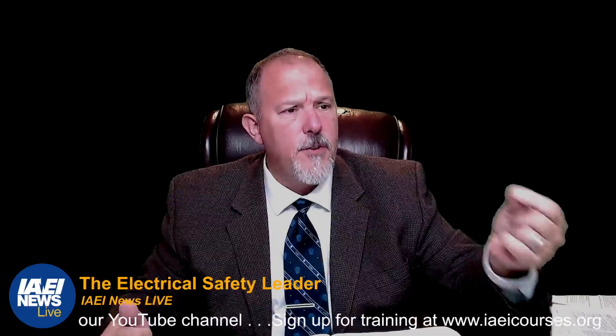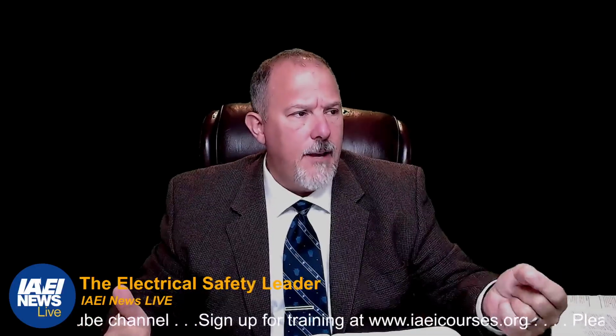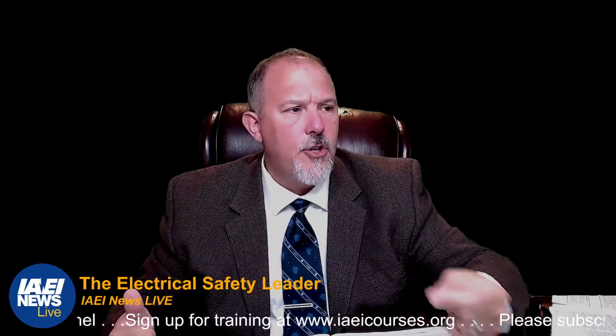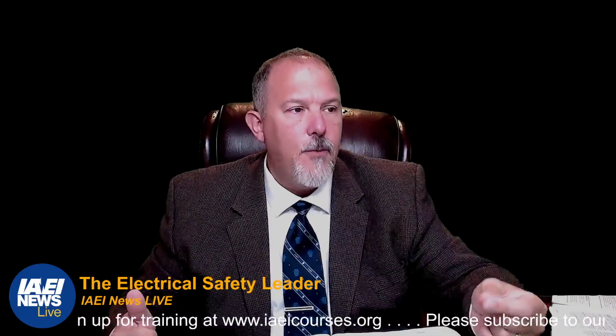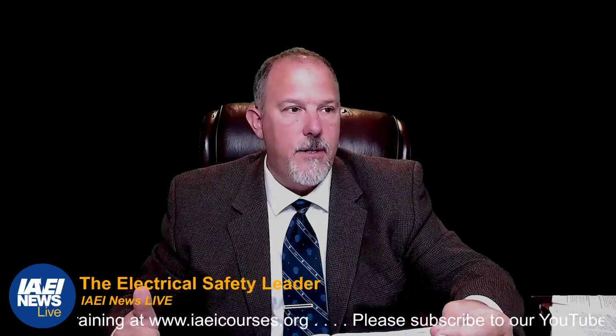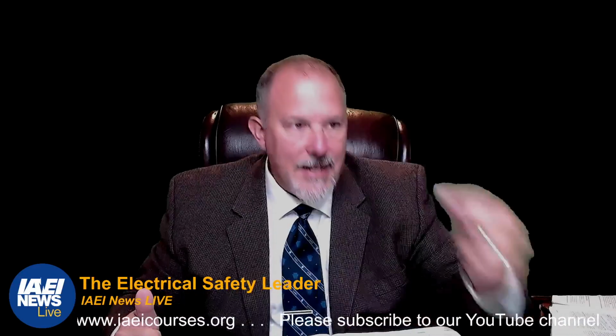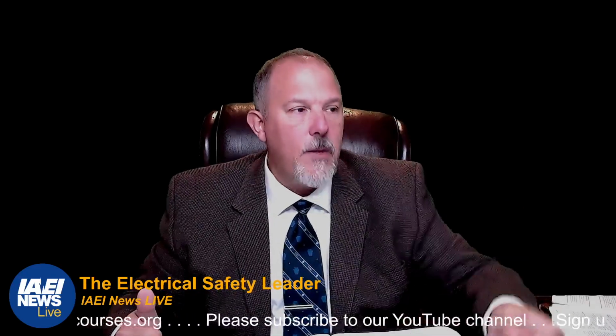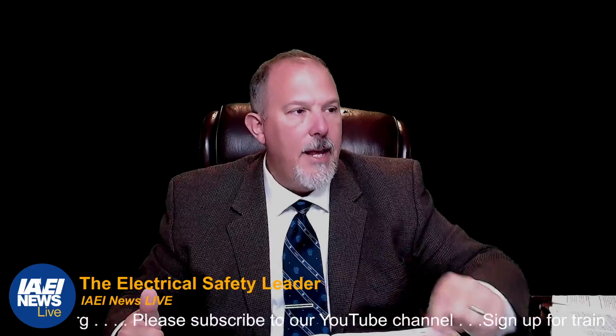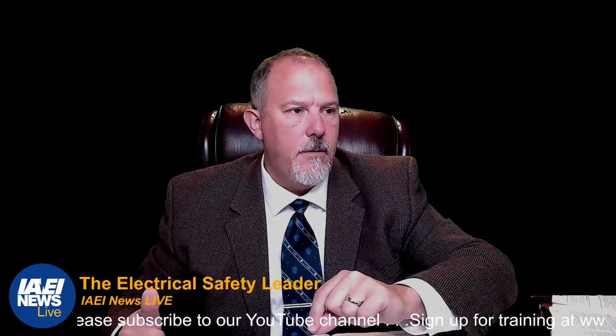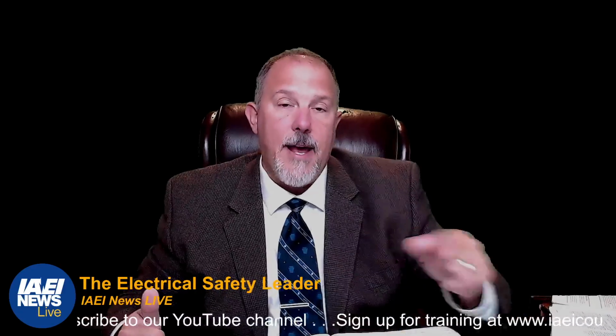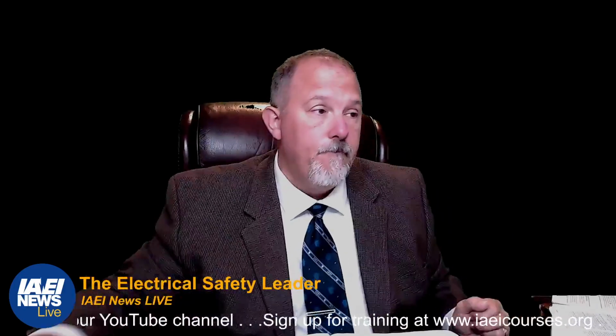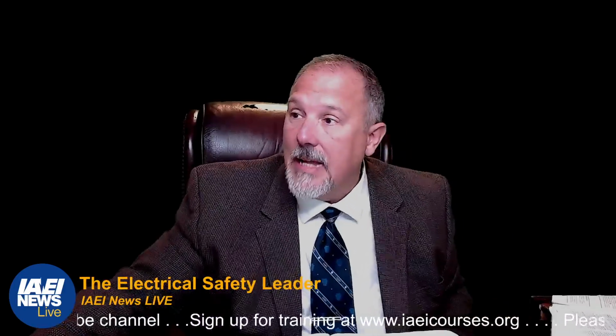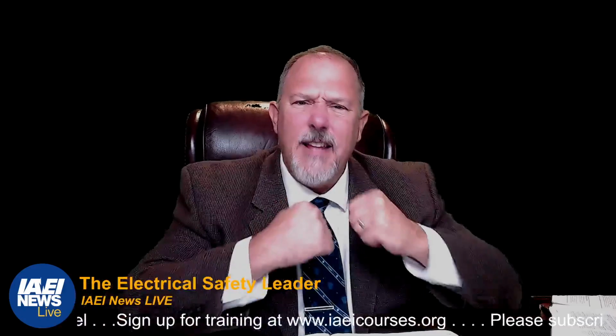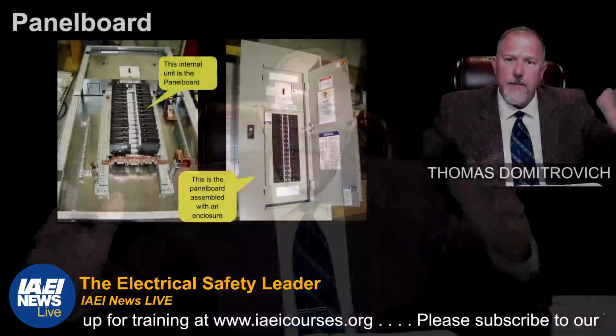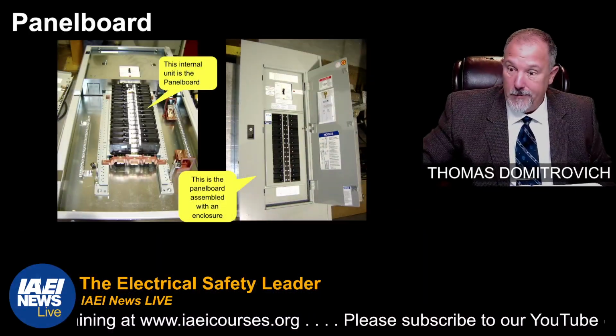Where the available fault current is greater than 10,000 amps, the panel board and enclosure combination shall be evaluated for the application. So if it's less than 10,000 amps, you don't have to evaluate the panel board and enclosure combination for the application. What does that mean to you? Do you like that language? Do you hate that language? Do you just want to hug that language and give it big kisses? I don't think so. But anyway, I would hope not.